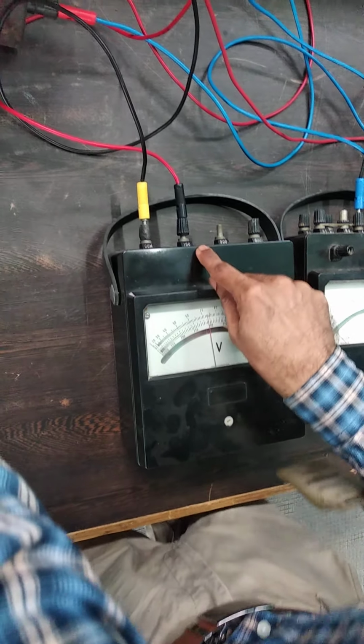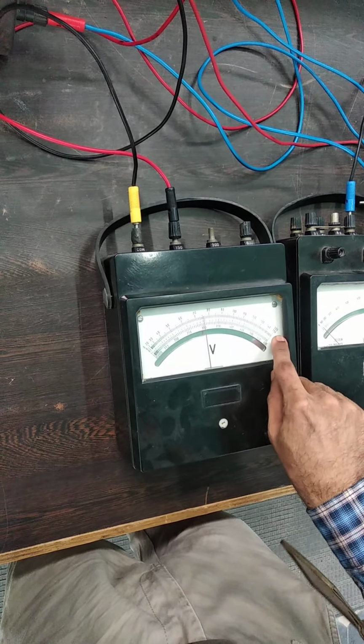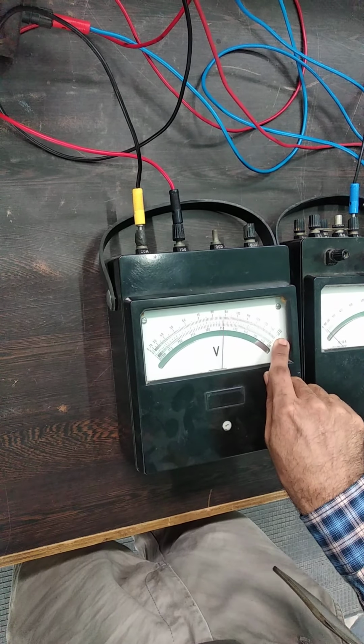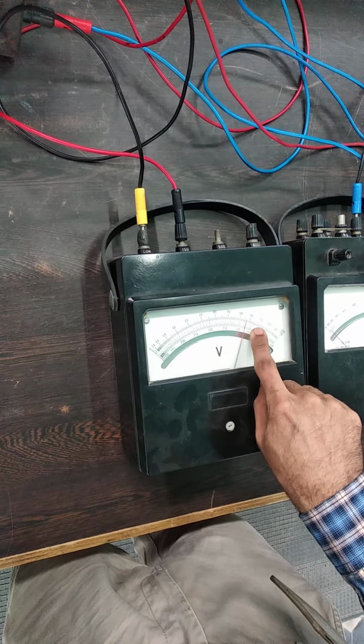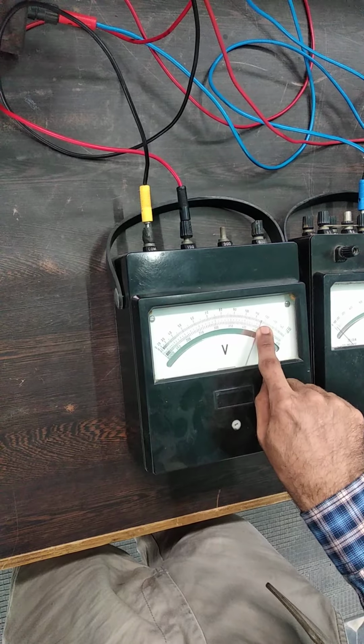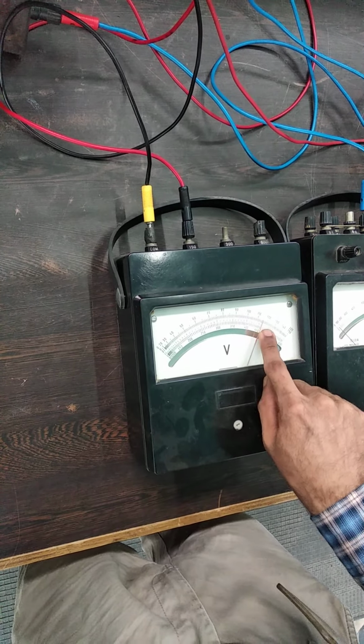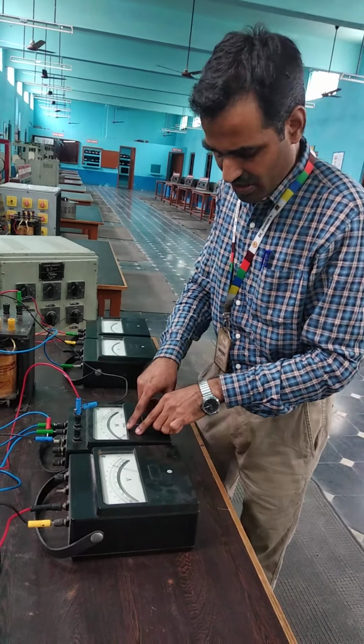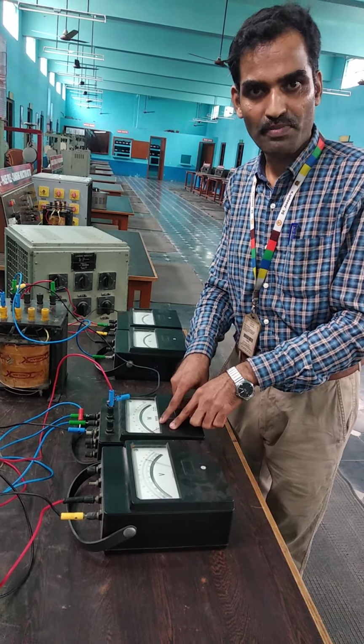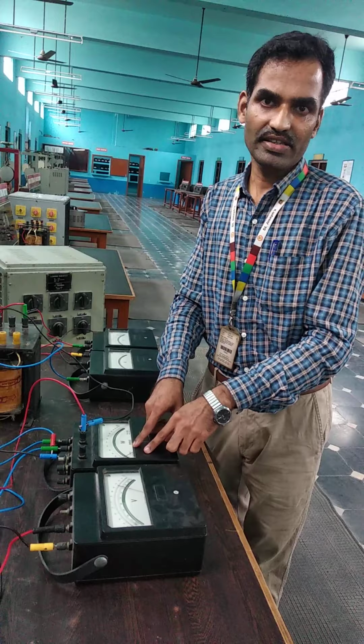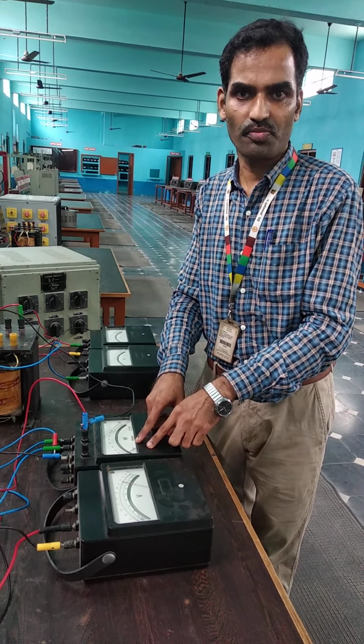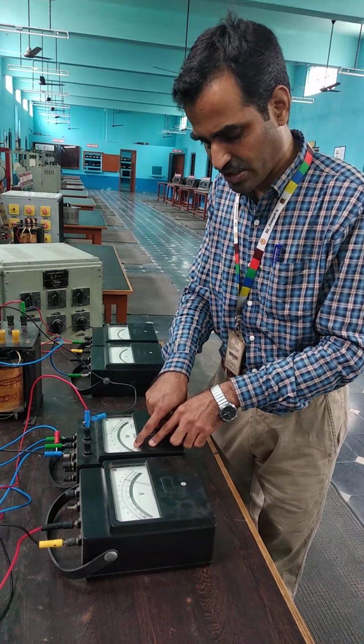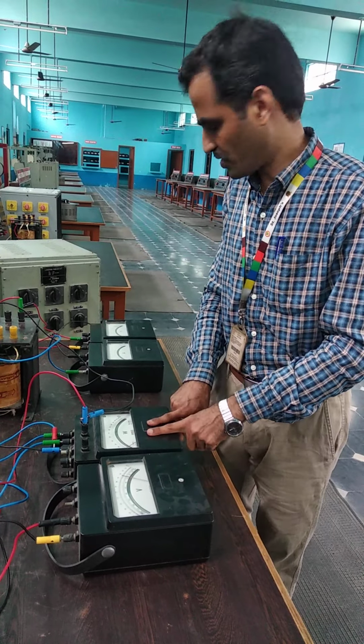I have connected the meter to 150, so I have to read this scaling in the 150 range. So this is my 115 volt. I set the meter to its 115 volt, and it can measure the input power, which will be very minimum, because you know from theory that the no load current of your transformer will be very minimum. So you measure this power. This is your input power.